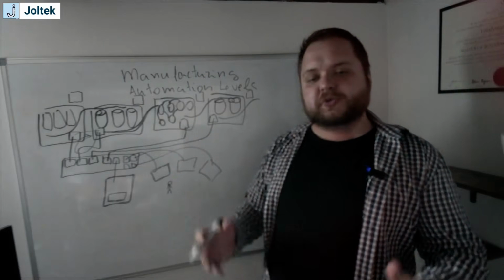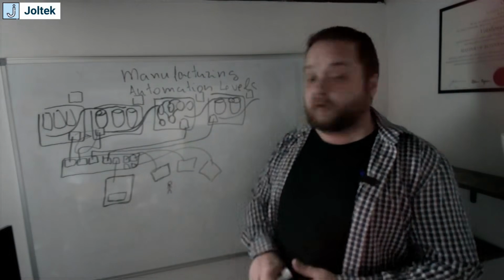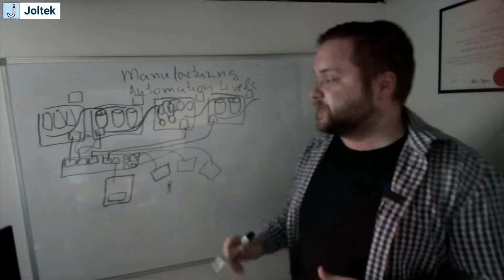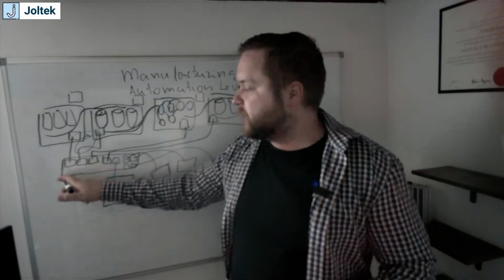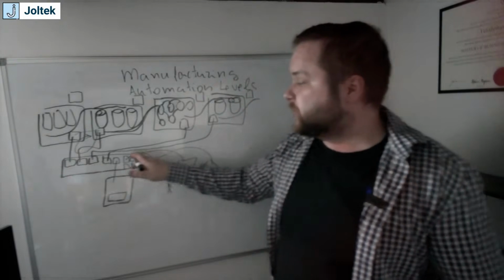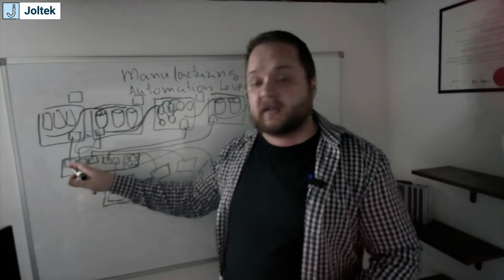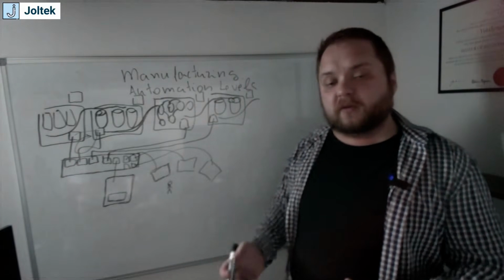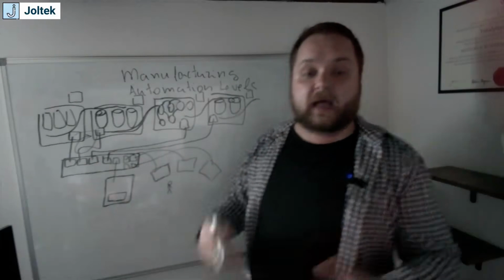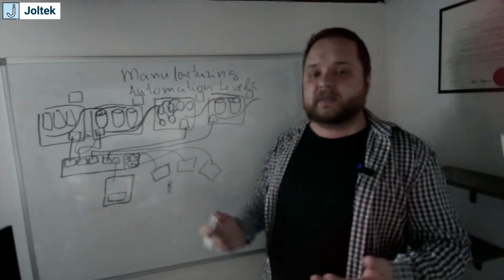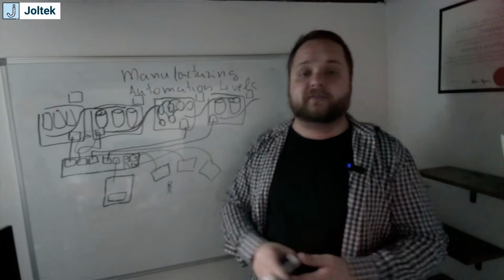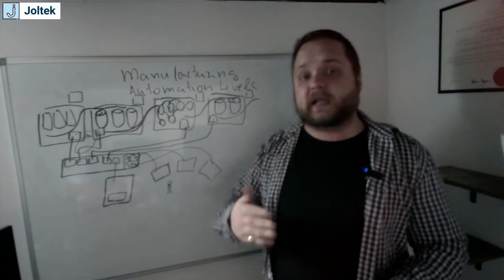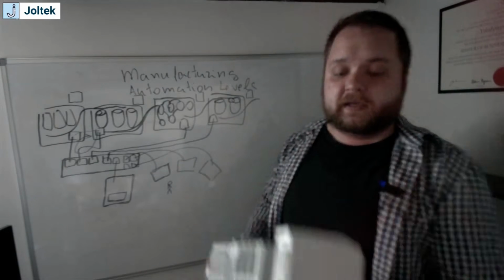So what does it usually take to get your networks in order? This is where you start having a managed architecture, right? So this switch usually is not going to be unmanaged. This switch needs to know exactly what sits at every port. And usually, again, when you have a smaller facility, you're going to have a flat network, right? And a flat network basically means that everything has the IP address of, for example, 192.168.1 or .0.xxx. And the reason for that is twofold, right?